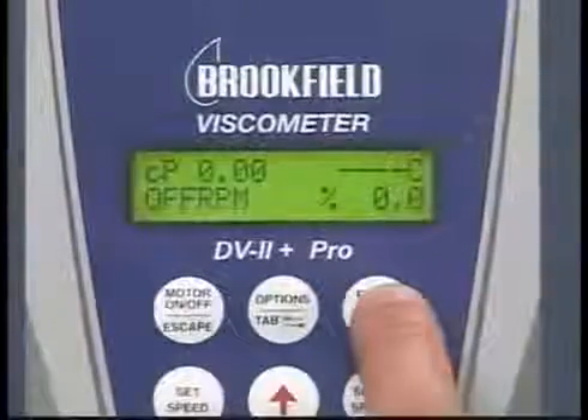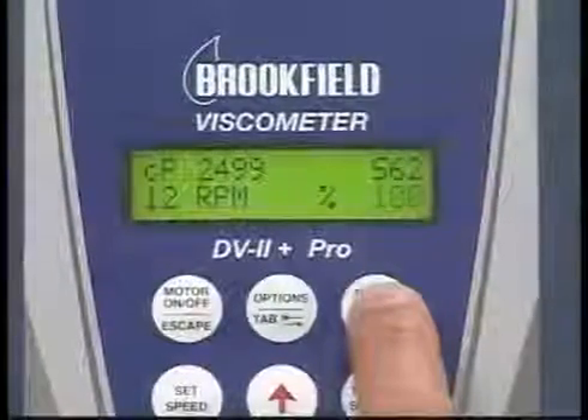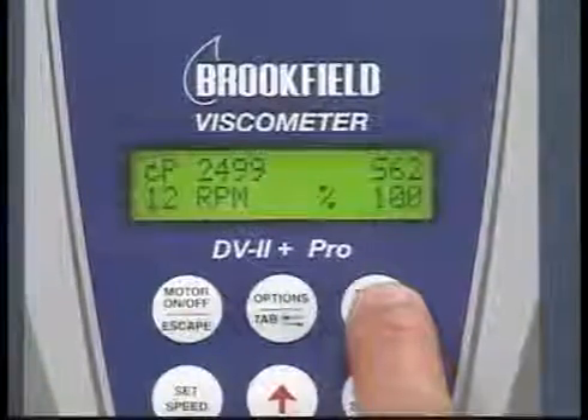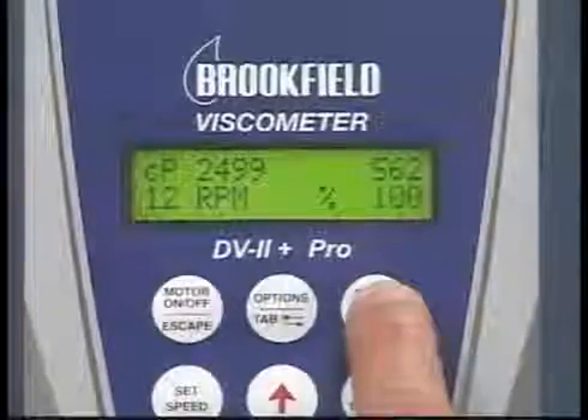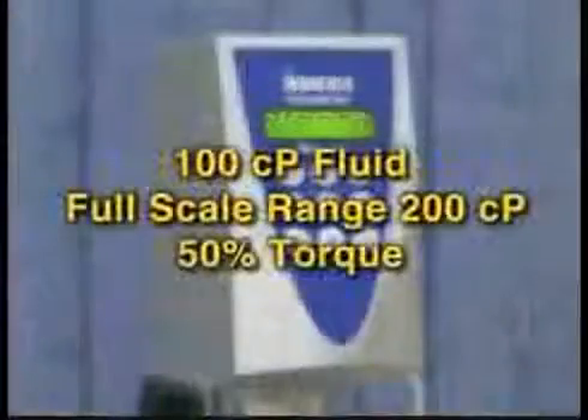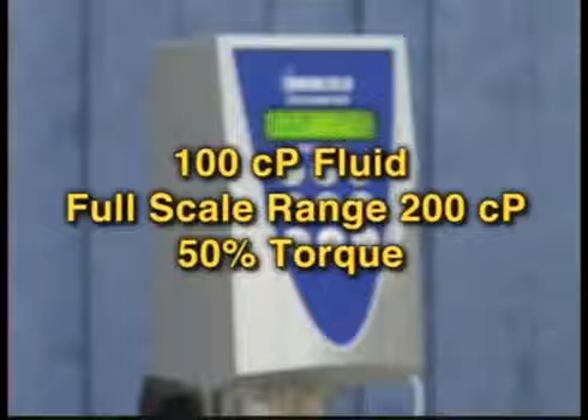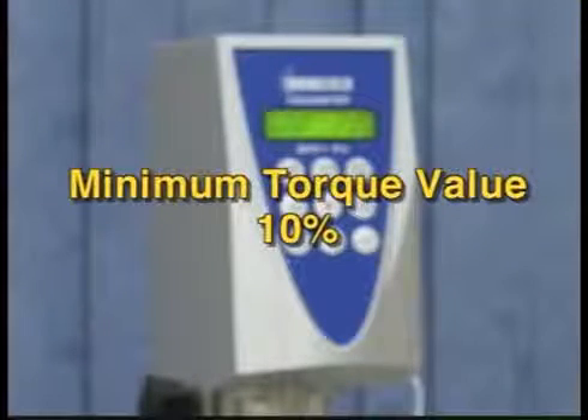With a digital instrument, you can easily find the full-scale range by turning on the motor and pressing and holding the auto range button. For example, if you are using a 100 centipoise fluid, a full-scale range of 200 centipoise will give you a 50% torque. The minimum torque value for a good reading is 10%.